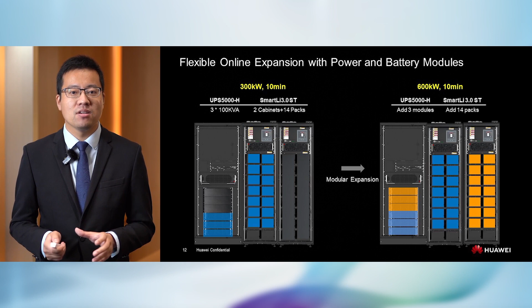It's not just theory. We really did the test. The left figure shows the imbalance current of the SmartLi 3.0. We find that from the starting point to the ending point, during the whole discharging duration, the imbalance current is only 2% to 5%. However, if we parallel the batteries directly, the imbalance ratio will reach 10% to 25%.